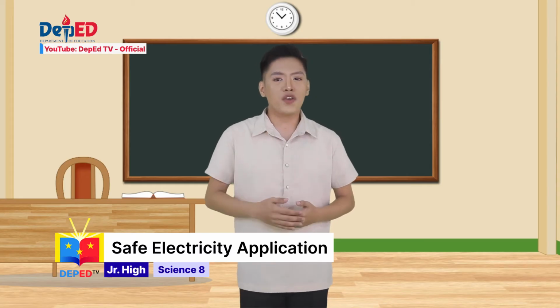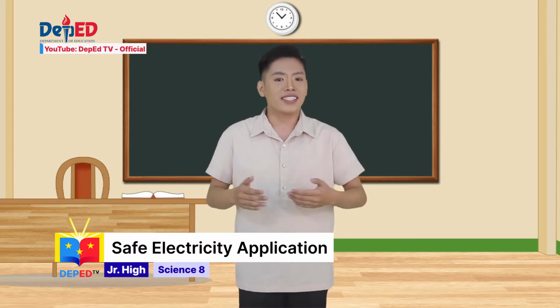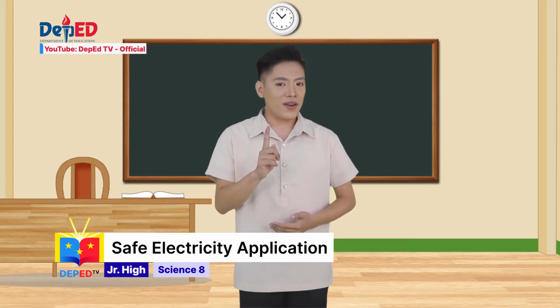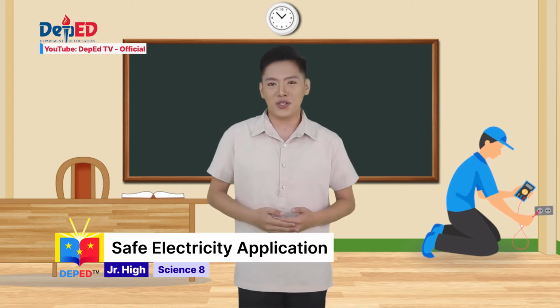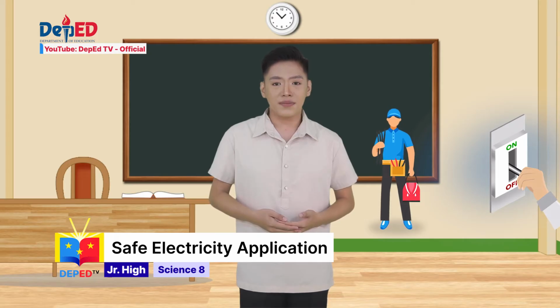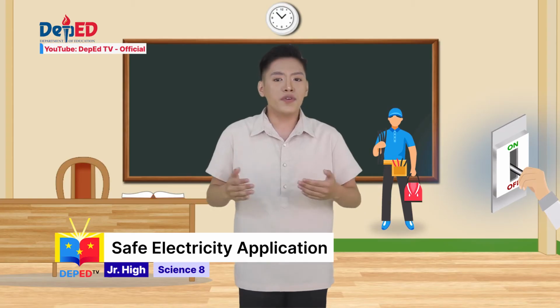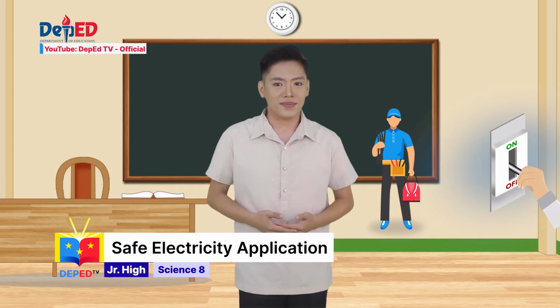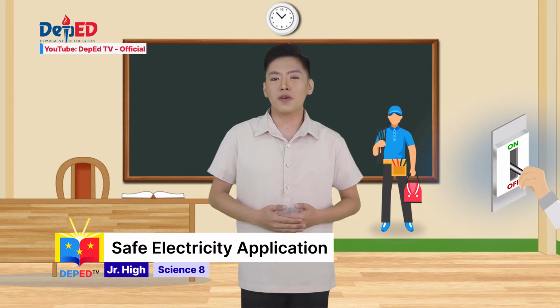So the practice of using only one hand, the other kept behind your back while working on high voltage circuits, is a very good safety habit. Even better would be to disconnect all sources of power from the equipment you are about to repair. Do not rely on insulated tool handles and rubber-soled shoes to protect you. It is better to shut down the main switch of a voltage source before doing any electrical repairs. Relying on insulated handles and rubber-soled shoes is not completely safe.